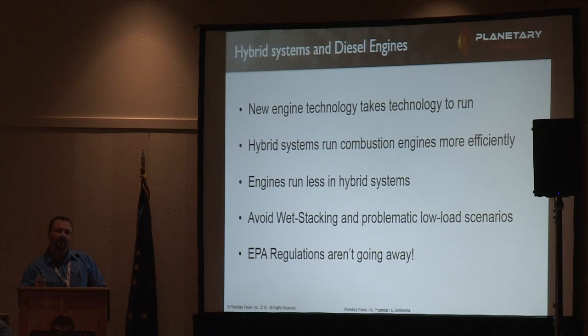In a hybrid situation, you can even go diesel off, and there's no better fuel efficiency than going to zero fuel consumption. Many times that's our goal — to go diesel off 50 to 75% of the time. The wet stacking and other problematic low-load scenarios can be virtually eliminated in a hybrid system when running the diesels at their maximum efficiency.